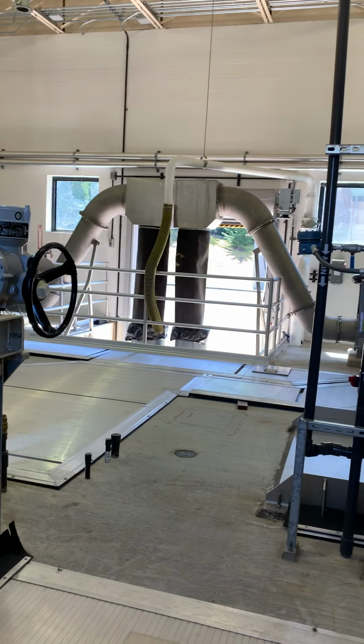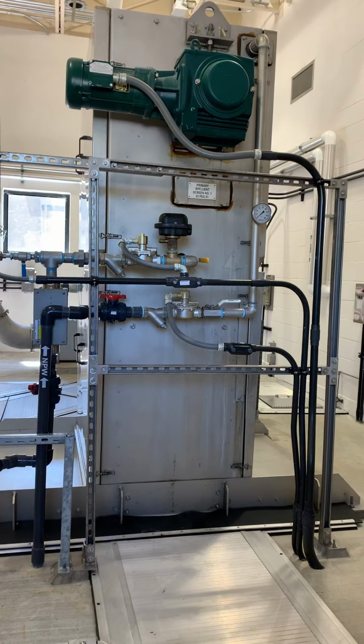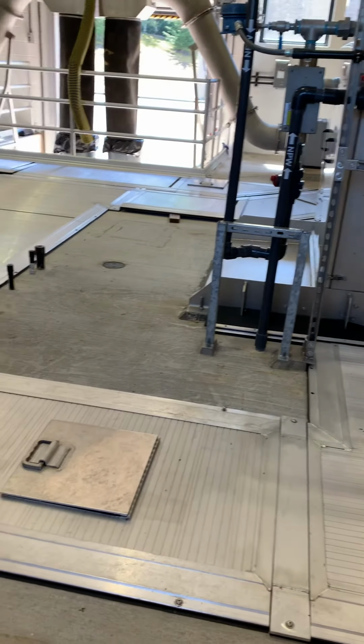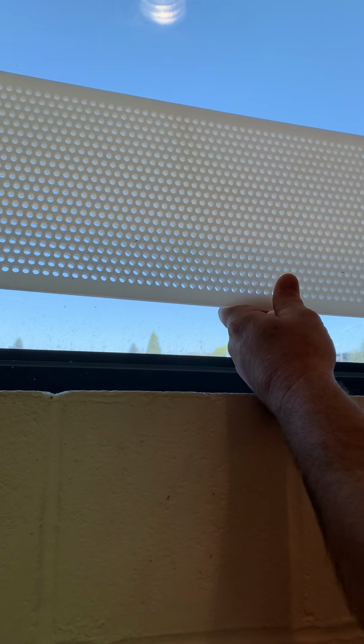So this is the primary machine room after the primary clarifiers. What we're going to do is screen it some more, because we screened it with 6mm band screens up in the headworks to get most of the trash out. I'll show you the size of those boards. The primary screening is a 6mm orifice. There are quite a few of these panels going around in a big circle in the primary screening devices. They pull out everything, and the washer compactors take care of a lot of that trash too.